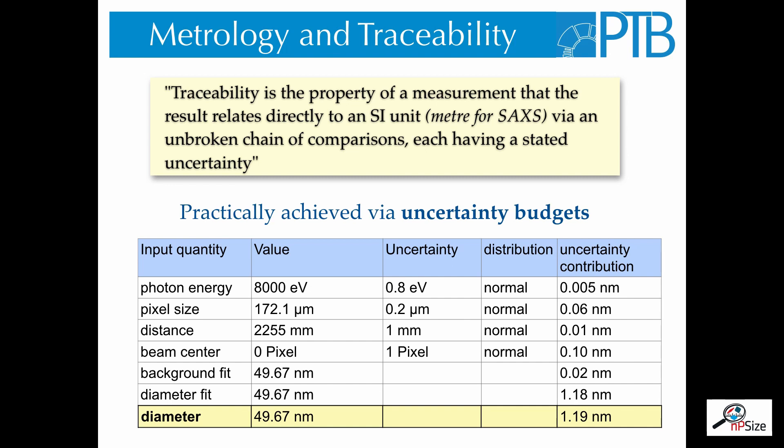In practice, we achieve this via a so-called uncertainty budget. At the bottom, you can see such an uncertainty budget. Each row of the uncertainty budget corresponds to an input quantity, which is required to compute the final value of the diameter, which is shown as the last row. For each of these input quantities, we determine the value, the uncertainty of the quantity, and how much it influences the final value, the so-called uncertainty contribution. In the end, we combine all of these uncertainty contributions into the total uncertainty of the diameter.